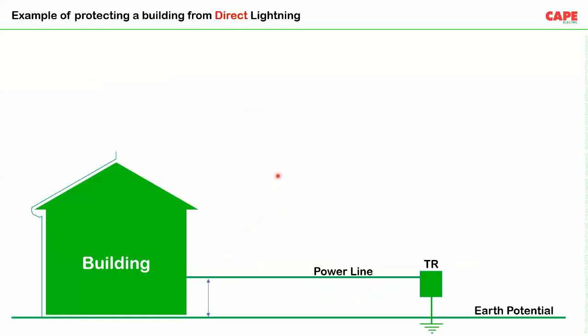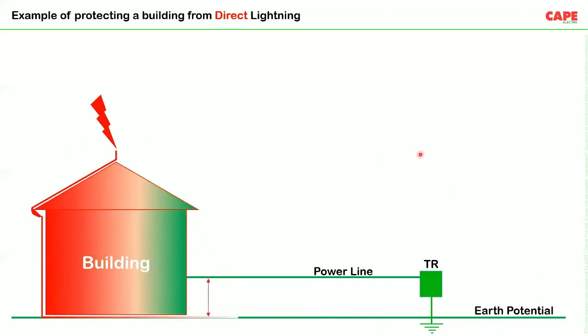Now, how does this device work during a lightning strike in your building? You have a building. You have a power line coming from a transformer. The star point of the transformer is connected to earth, and here this green line means under normal conditions everything is at reference to the earth potential. You have a very safe system. Imagine there is a lightning strike. The lightning current flows through the down conductor. It flows to the earth. As a result, some portion of the building will have a high potential, some portion of the building will have a different potential. It depends on various parameters.